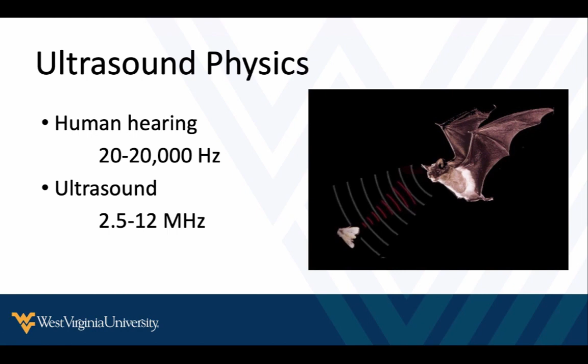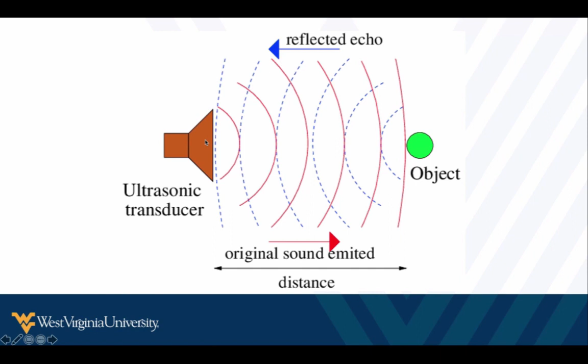And what I really want you to understand is, one, we're sending sound into tissue, the sound bounces back from the tissue into the transducer, but the most important functioning and working parts of ultrasound are actually in the transducer itself that's in contact with the patient. And so you don't want to drop those things, you don't want to break them, and you want to take care of them. But that's where the sound is generated, and that's how it's also received.